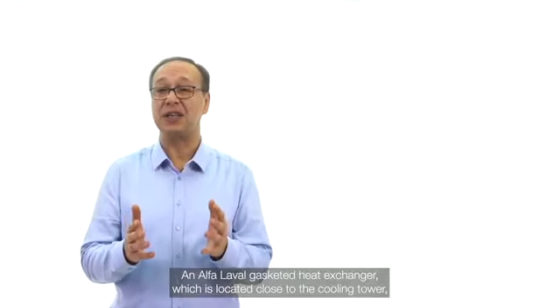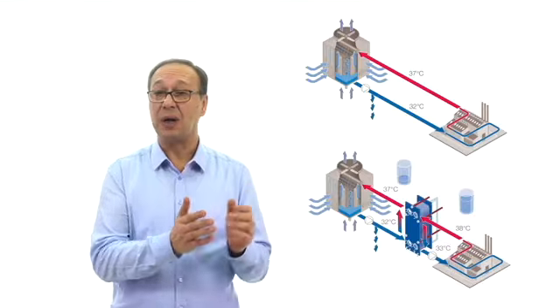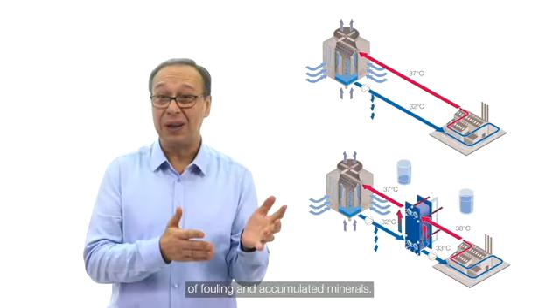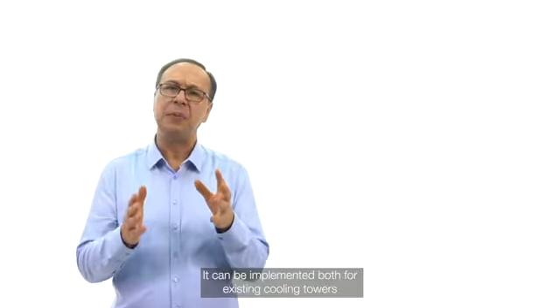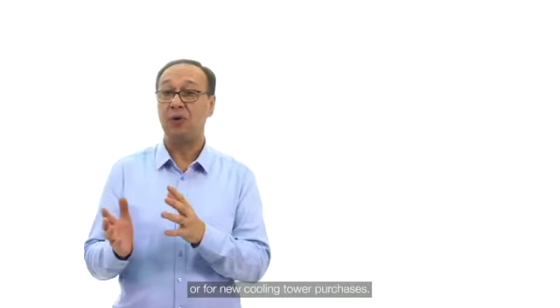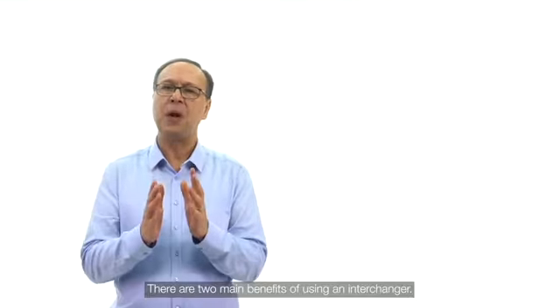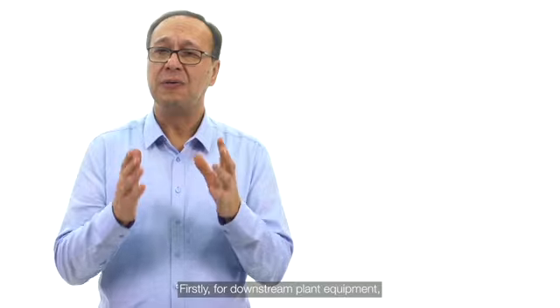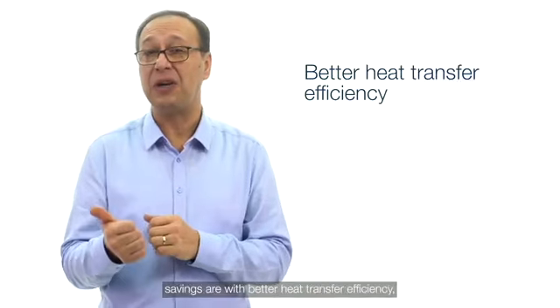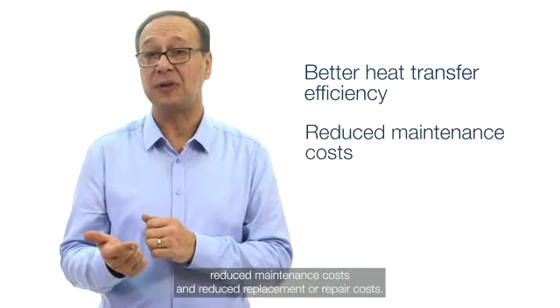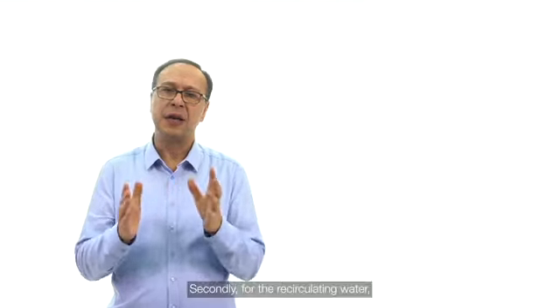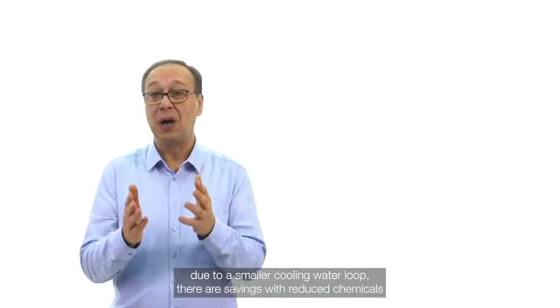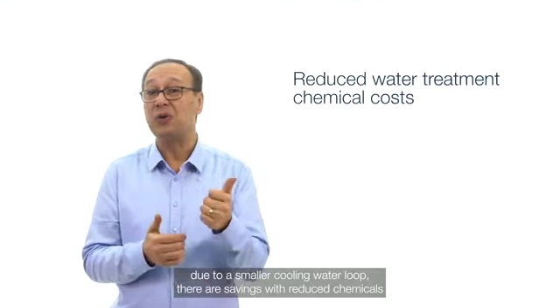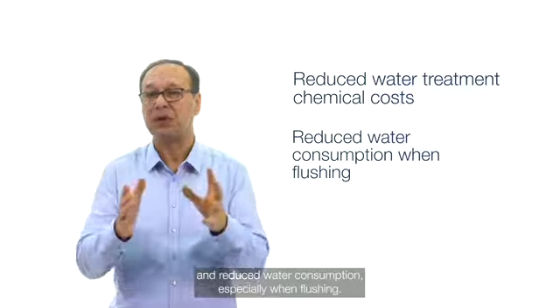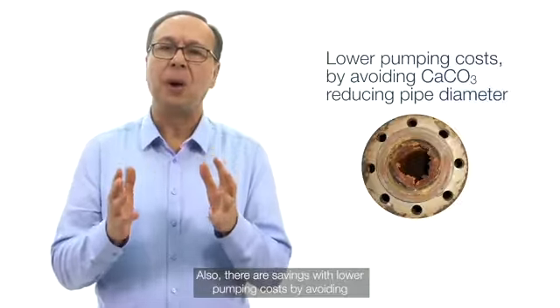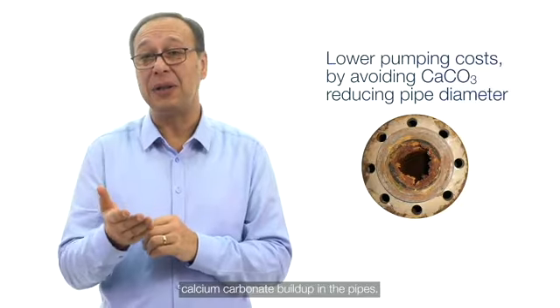An Alfa Laval gasketed heat exchanger, which is located close to the cooling tower, will protect the plant from the harmful effects of fouling and accumulated minerals. It can be implemented both for existing cooling towers or for new cooling tower purchases. There are two main benefits of using a heat exchanger. Firstly, for downstream plant equipment, savings are with better heat transfer efficiency, reduced maintenance costs, and reduced replacement or repair costs. Secondly, for the recirculating water, due to a smaller cooling water loop, there are savings with reduced chemicals and reduced water consumption, especially when flushing. Also, there are savings with lower pumping costs by avoiding calcium carbonate buildup in the pipes.